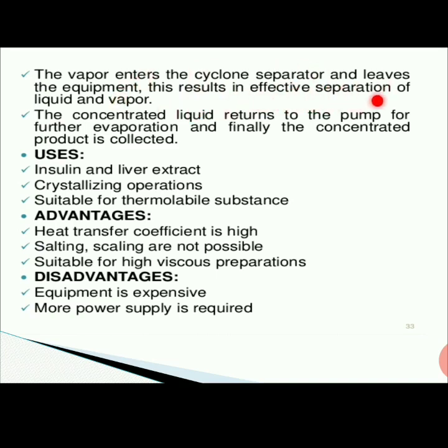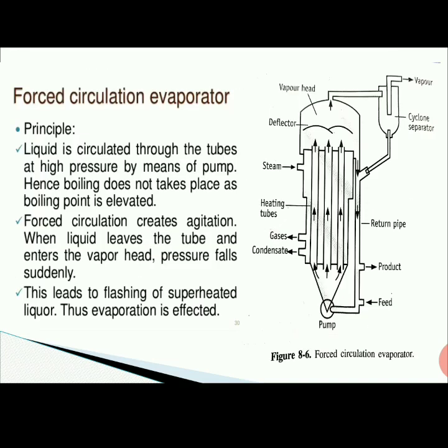This results in effective separation of liquid and vapor. The concentrated liquid returns to the pump for further evaporation, and finally the concentrated product is collected from the bottom side. When liquid enters the pump, the pump gives high velocity to the liquid, and the liquid is thrown into these tubes. Then due to the hot steam, the liquid gets heated up.